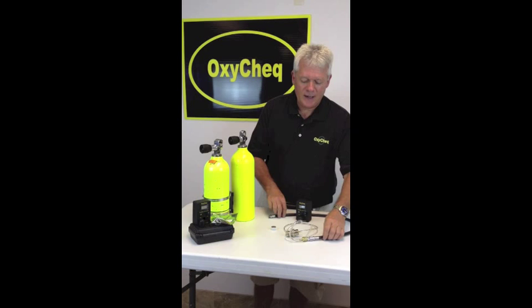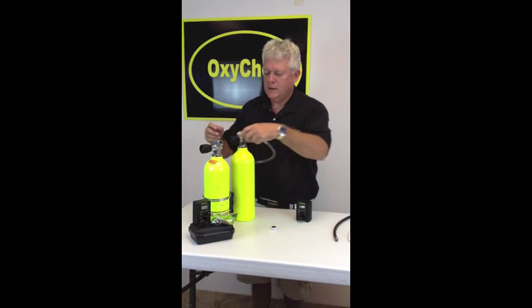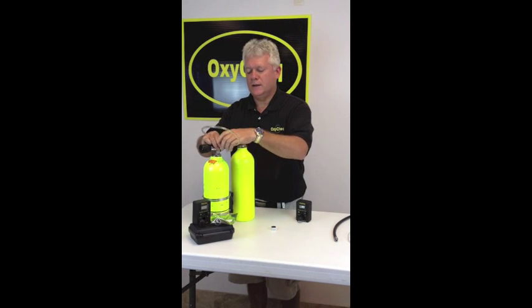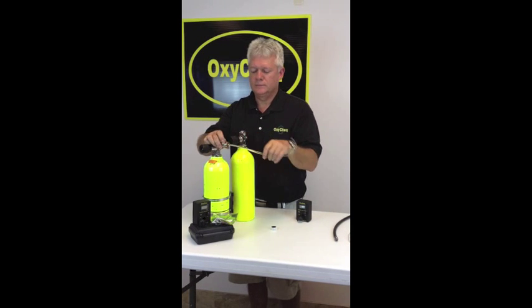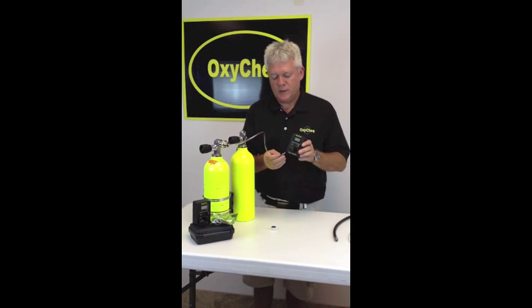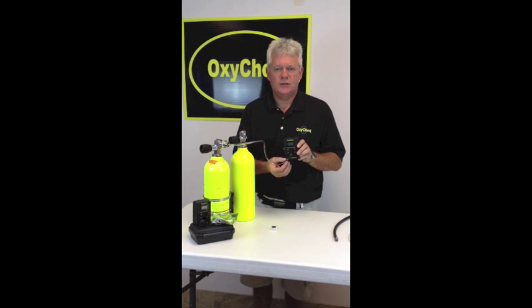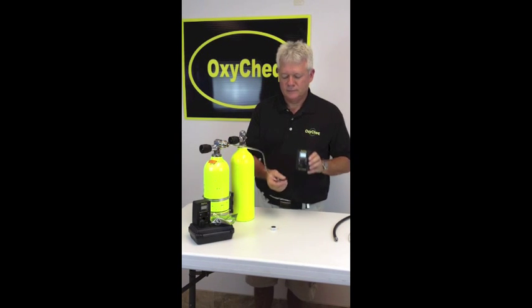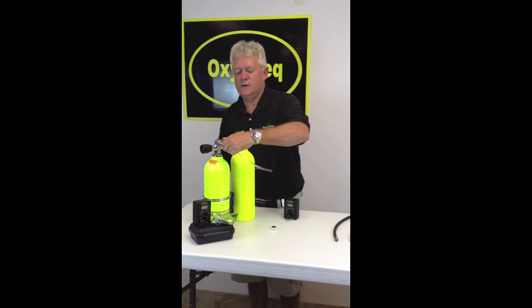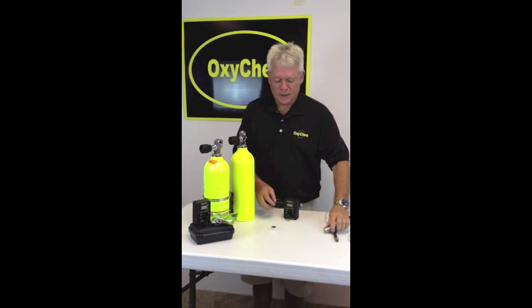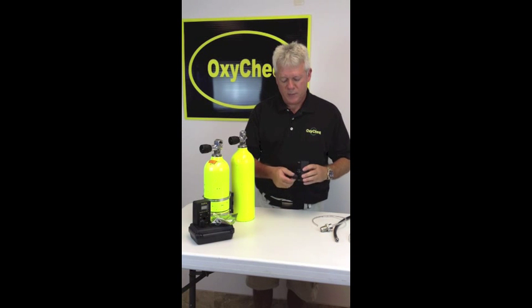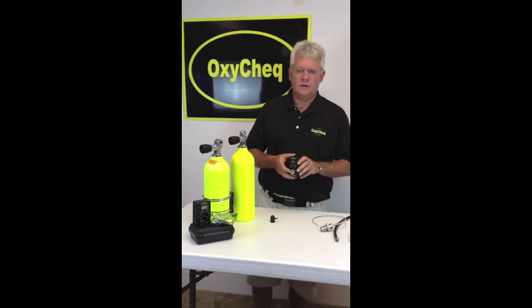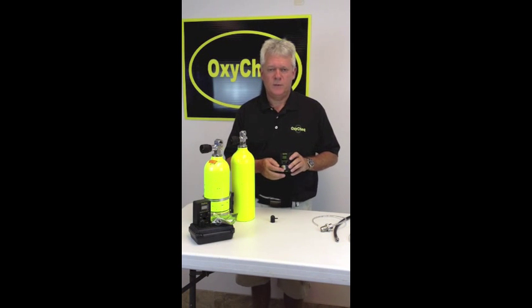If you were using a DIN valve, that could be screwed directly into the DIN valve itself. The valve could be open and it would attach to the nipple on the flow cap. One other accessory worth considering is the sensor saver. Prior to storage, you'd be taking your flow cap off and you could put the sensor saver right onto the analyzer itself. What that would do is increase the life of the sensor by anywhere from 2 months to 4 months depending on use.